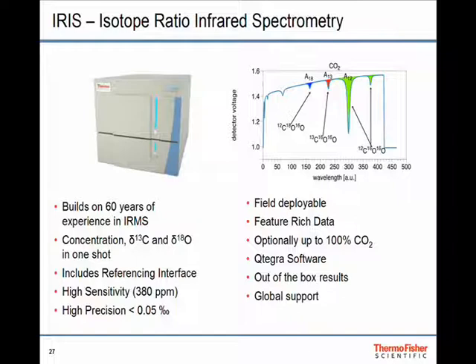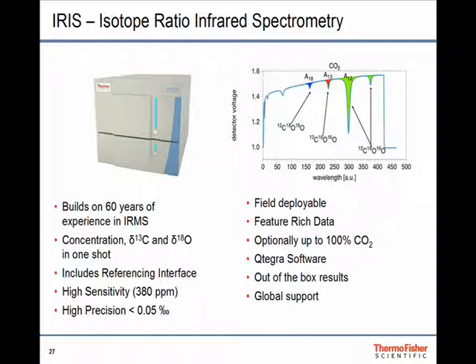Summarizing, we build on 60 years of experience with IRMS. You get concentration, 13C and 18O in one shot. You include the reference interface to give you long-term stability. It works very well at 380 ppm. You can get 0.05 per mil precision. It's field deployable. You get these feature-rich data sets that tell you a lot about your experiments. We have software that I didn't talk much about. You get out-of-the-box results. You set it up and start measuring right away.